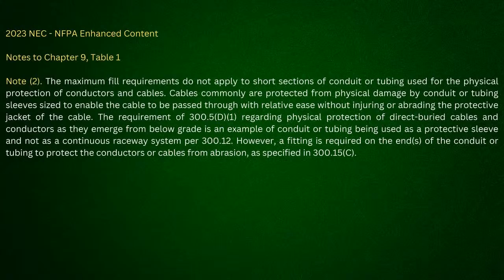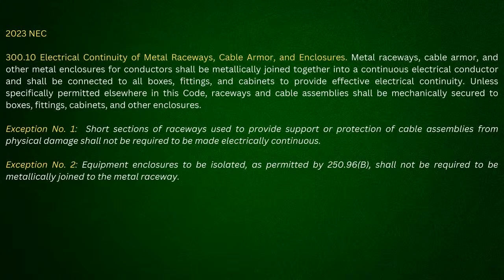Now, I'm going to show you different parts in the code. We'll go look at 300.10, 300.12, and I'm going to show you where it uses that exact term there, short sections. Now, the second sentence says, cables commonly are protected from physical damage by conduit or tubing, sleeves, sized to enable the cable to be passed through with relative ease without injuring or abrading the protective jacket of the cable. Now, how anybody's going to disagree with it up to this point, I don't get it, because I'm showing you here, even NFPA is recognizing these short sections now.